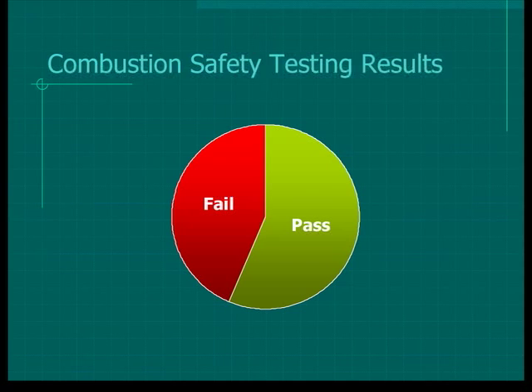Let's take a look at the combustion safety testing we've done. It's part of the audit, and also done after retrofits, so if they're doing air sealing on your house, this test is done in the test-out phase before you get your rebate from the city of Fort Collins. 45% of the houses we tested failed the combustion safety test. That means the picture from the beginning, with combustion byproducts spilling into the house, was happening for at least 60 seconds on startup. So it's a serious issue. I applaud the city of Fort Collins for putting this in their program and only rebating once this safety issue has been addressed.